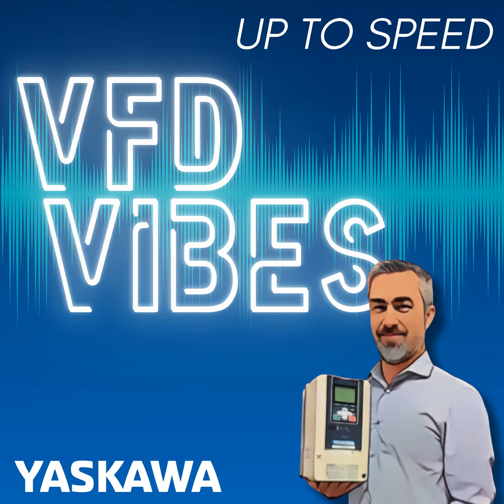Now, S1 is represented by the digit all the way to the right. And if that's a 1, I know that S1 and SN is closed. So the service tech might say, yeah, they're all zeros. And I'd say, okay, you don't have an active run command. He said, no, that's not the case. I have 9 other drives. They're all running. This is the last drive on the line.